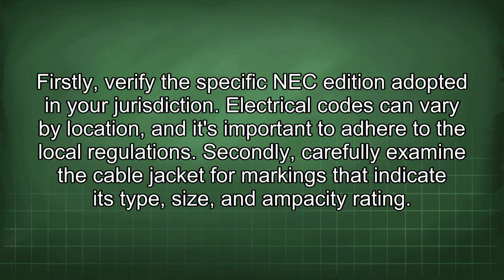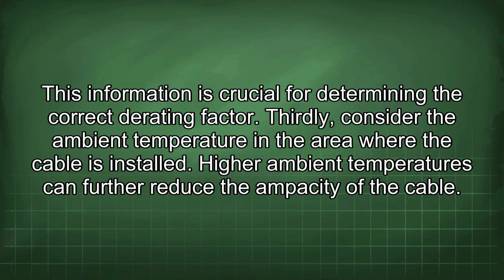Firstly, verify the specific NEC edition adopted in your jurisdiction. Electrical codes can vary by location, and it's important to adhere to the local regulations. Secondly, carefully examine the cable jacket for markings that indicate its type, size, and ampacity rating. This information is crucial for determining the correct derating factor.